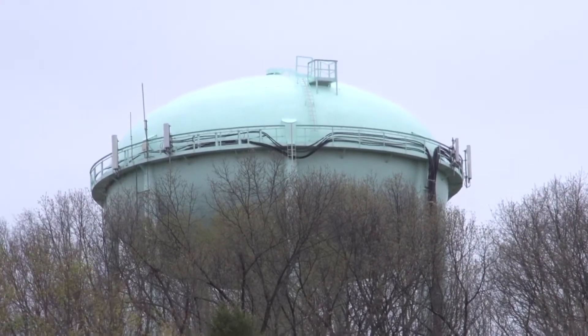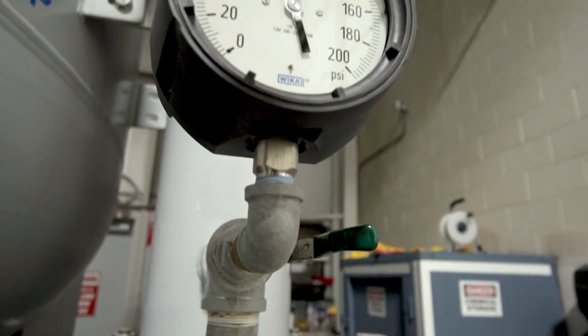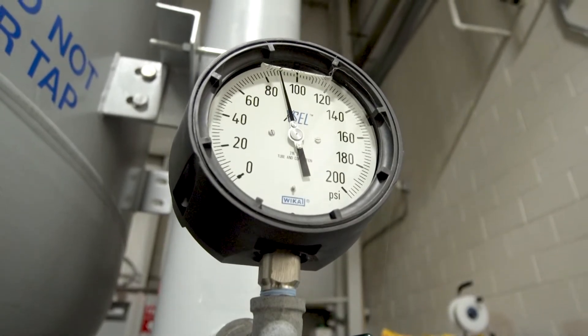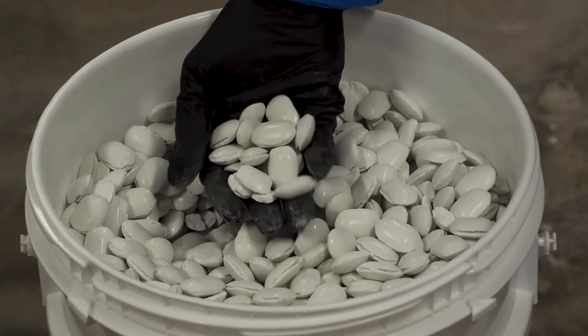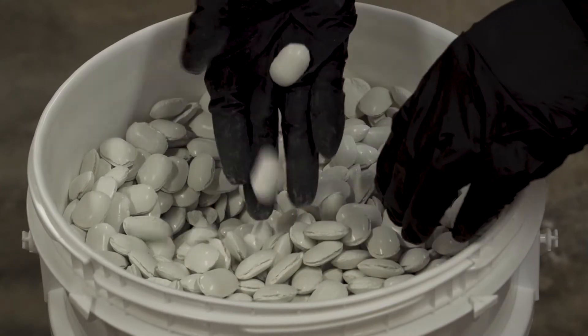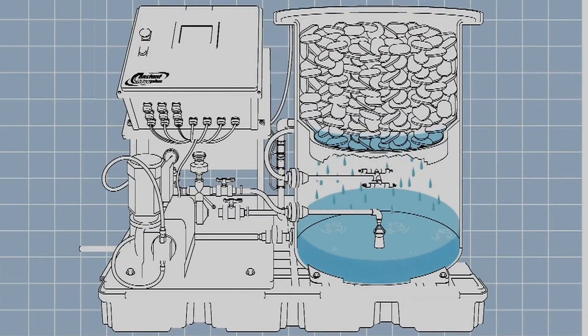With gas, they had found a 20-minute delay in the chlorine residual. Using the Lonza system, they did not see that. The Constant Chlor Plus system utilizes a spray technology. It starts with a briquette made in a pillow-shaped form, so when it's in the basket there are not many air pockets between the briquettes. When you spray the briquette with that spray technology, you get a constant chlorine solution developed in the tank, which they use to disinfect their water.